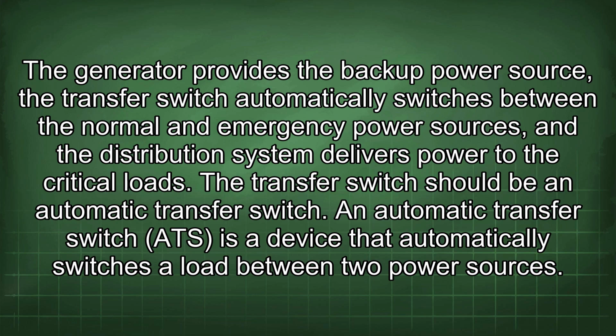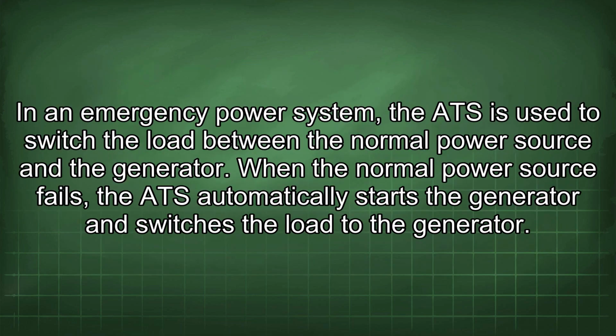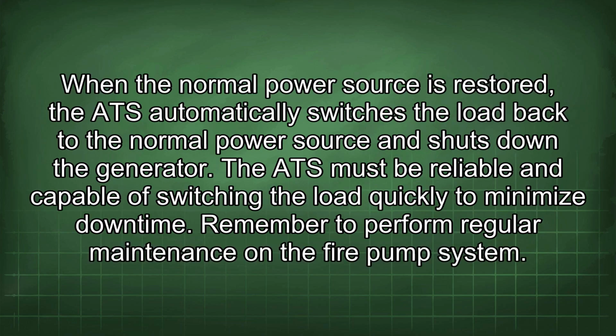An automatic transfer switch (ATS) is a device that automatically switches a load between two power sources. In an emergency power system, the ATS is used to switch the load between the normal power source and the generator. When the normal power source fails, the ATS automatically starts the generator and switches the load to the generator. When the normal power source is restored, the ATS automatically switches the load back to the normal power source and shuts down the generator. The ATS must be reliable and capable of switching the load quickly to minimize downtime.